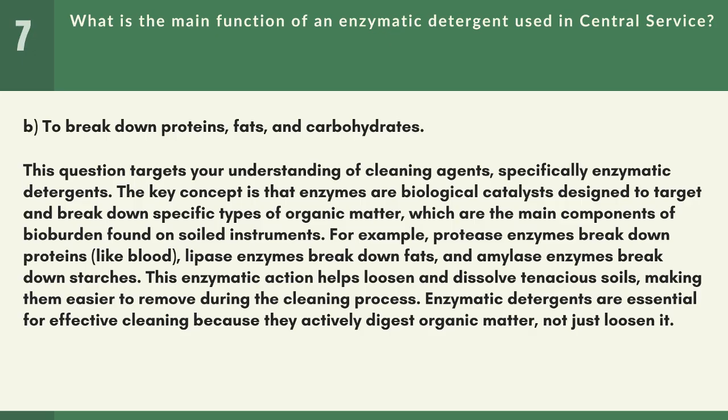This question targets your understanding of cleaning agents, specifically enzymatic detergents. The key concept is that enzymes are biological catalysts designed to target and break down specific types of organic matter, which are the main components of bioburden found on soiled instruments. For example, protease enzymes break down proteins, like blood, lipase enzymes break down fats, and amylase enzymes break down starches. This enzymatic action helps loosen and dissolve tenacious soils, making them easier to remove during the cleaning process. Enzymatic detergents are essential for effective cleaning because they actively digest organic matter, not just loosen it.